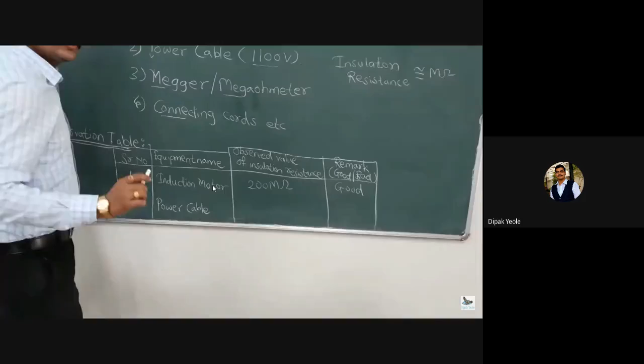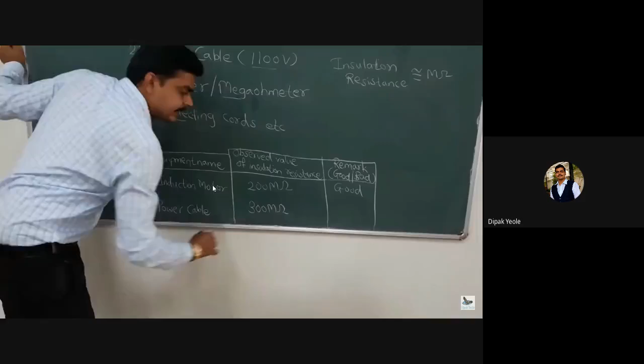The second reading, observed for our power cable, comes to 300 mega ohm, and since this value also lies in terms of mega ohm, the remark is good. So for both electrical equipments tested for insulation resistance, we observed the condition is good.